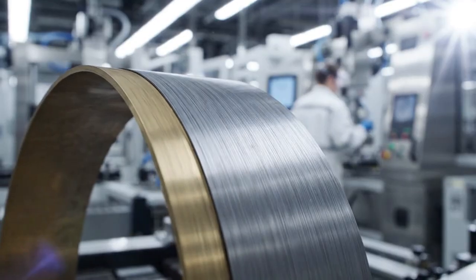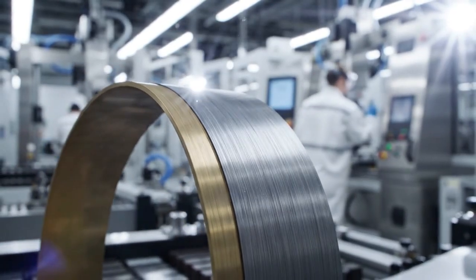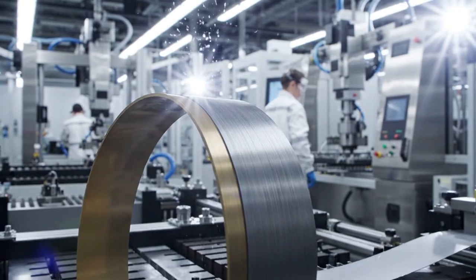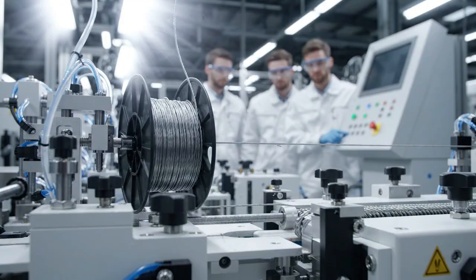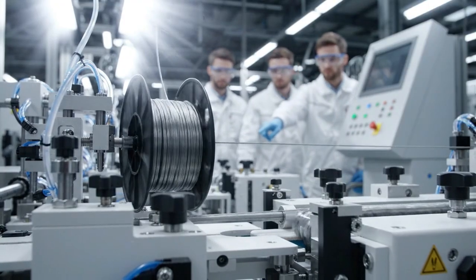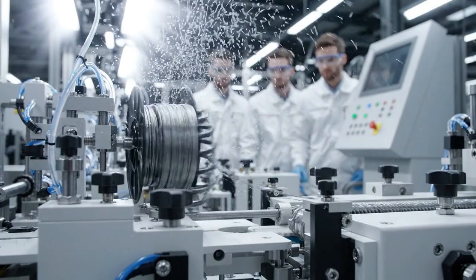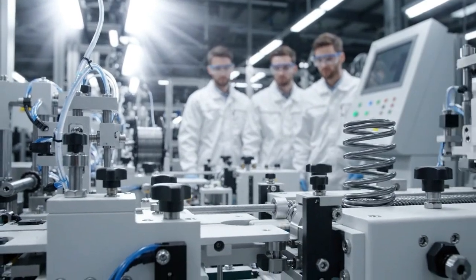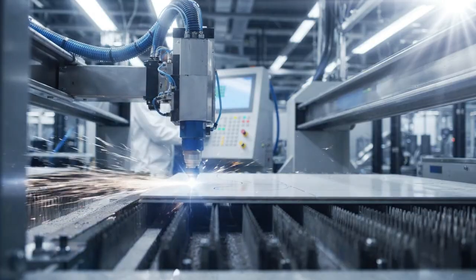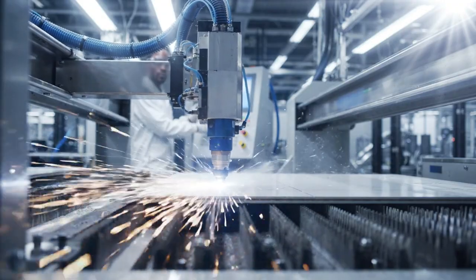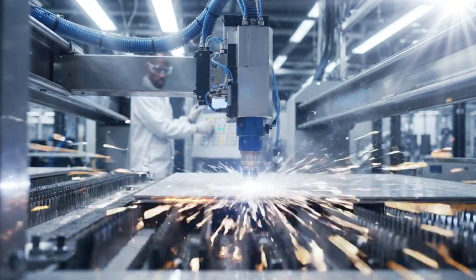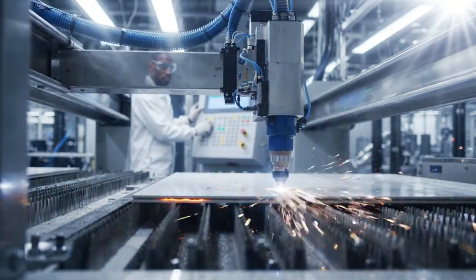The bimetallic strip is the breaker's thermal brain. Two metals bonded together expand at different rates when heated. Trip springs must store enough energy to accelerate the contacts apart at extreme speed during a short circuit. Opening time is measured in milliseconds. Arc chute plates divide the fault arc into multiple smaller arcs, dramatically increasing the total arc voltage and enabling rapid extinction of the dangerous arc.